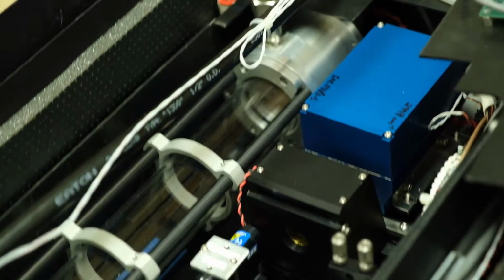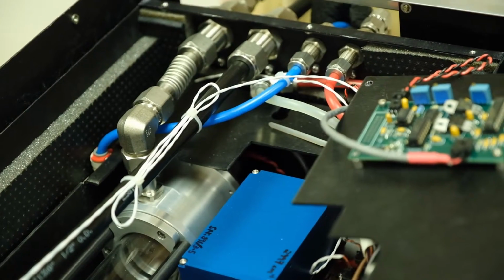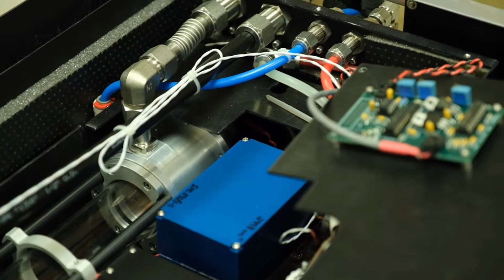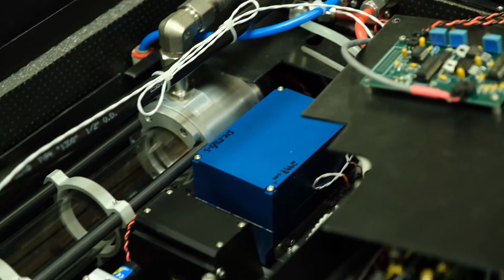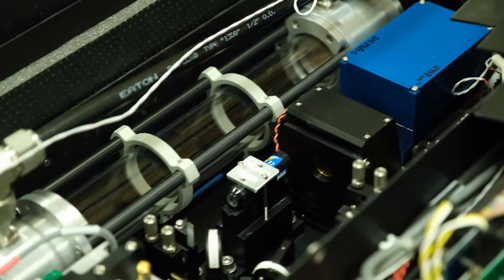Wow. So the laser is what's actually detecting. Yeah, so the laser is designed to hit a specific wavelength for the gas that we're interested in. And it's collected through, and you tune it over a wavelength range where that gas absorbs. And so if there's more N2O present, then the signal we measure at the end has less signal. And that's how we can actually determine that.